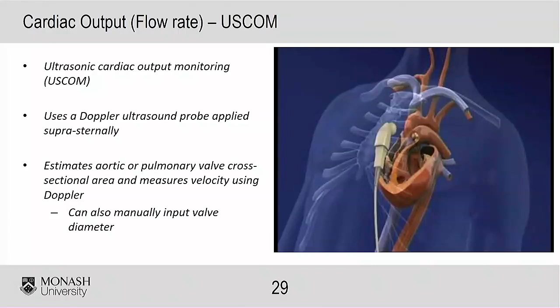So it uses a Doppler ultrasound probe, you can see it here, that's applied suprasternally, so it's just on the chest, just above the sternum here, and it's facing towards the arteries here. So you get pretty close with this probe. And it estimates the aortic or pulmonary valve cross-sectional area, and then it uses Doppler to measure the velocity. And if we know the velocity and the area, we can calculate the cardiac output, obviously. You can also input the valve diameter if you don't think it's doing a very good job of estimating this.